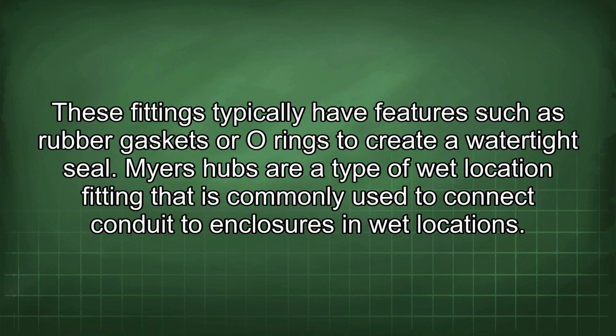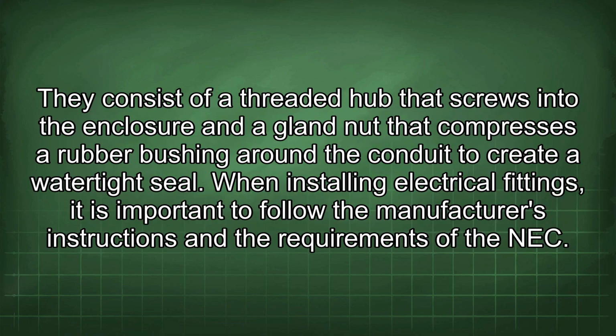These fittings typically have features such as rubber gaskets or O-rings to create a watertight seal. Myers hubs are a type of wet location fitting that is commonly used to connect conduit to enclosures in wet locations. They consist of a threaded hub that screws into the enclosure and a gland nut that compresses a rubber bushing around the conduit to create a watertight seal.